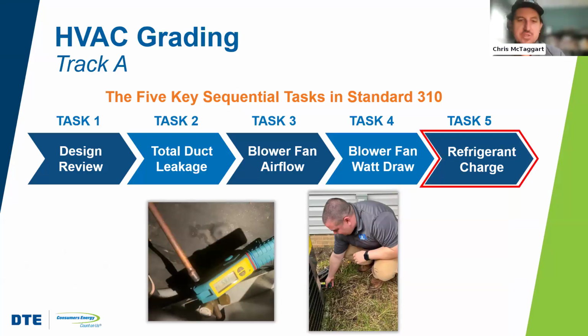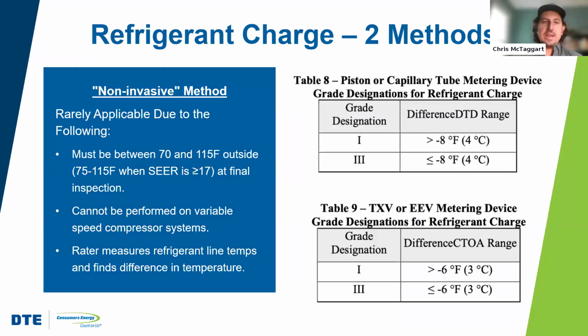And then finally, refrigerant charge. So my colleague Zach Mullins from BER is illustrating using a pipe clamp thermometer, which can tell us the temperature on the refrigerant lines, and that is one of the subcomponent values for the non-destructive testing method that raters oftentimes apply for testing refrigerant charge verification. And so, again, this non-invasive method allows for testing to be performed without an actual physical measurement of the refrigerant. It's based off of temperature conditions, both indoors and out, as well as measurement of the refrigerant pipes. So there is a process and some math that goes into it, but it at least allows for a non-destructive method of testing.